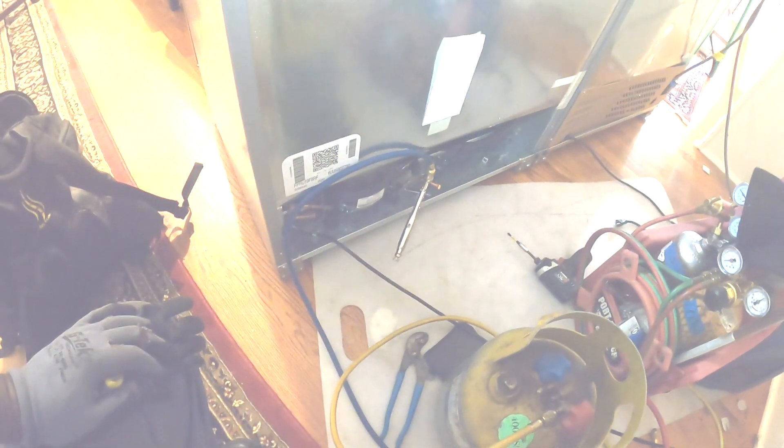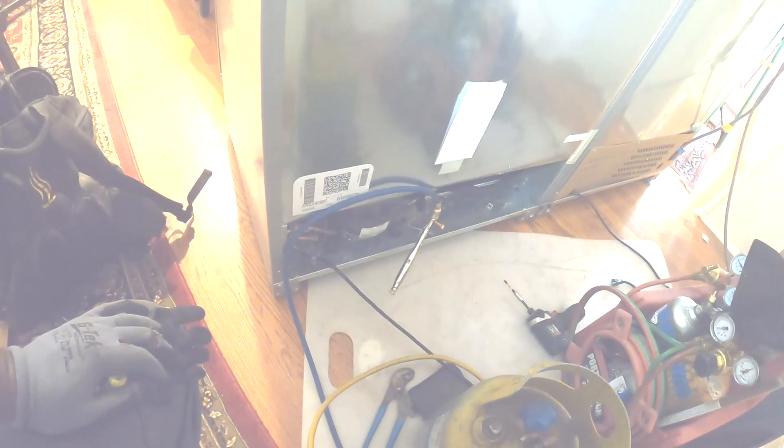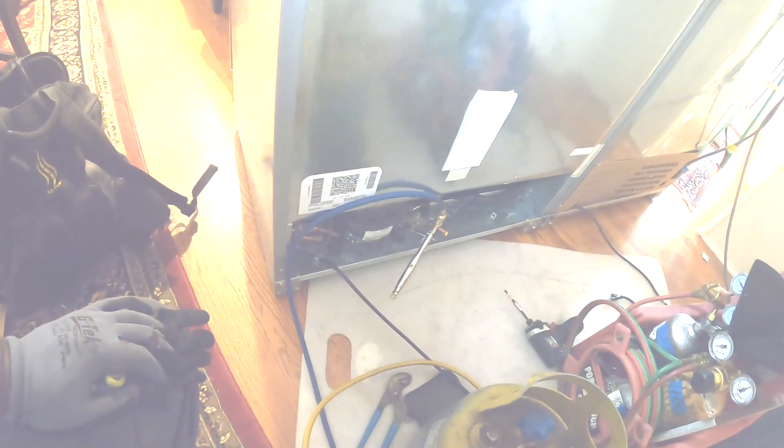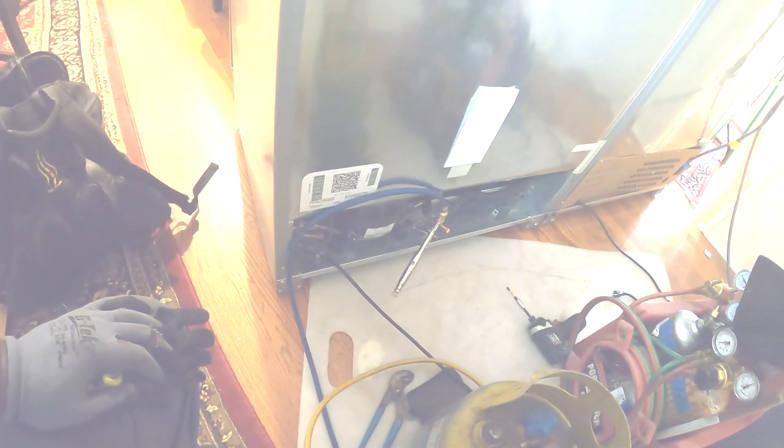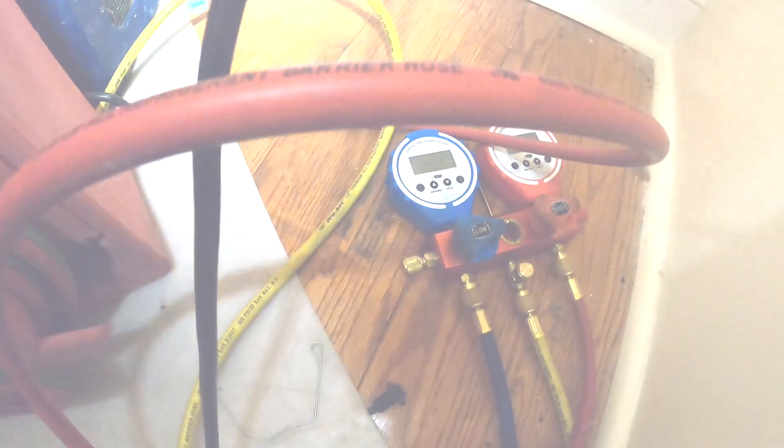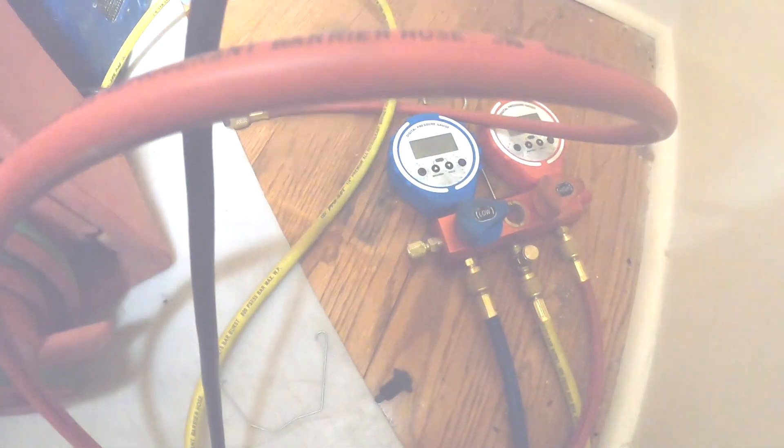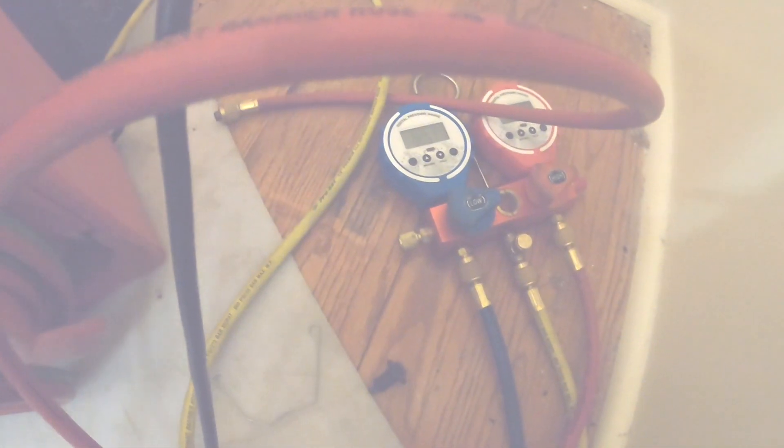I'm getting a slight frost on the evaporator coil, so I know the compressor is pushing and there's a little bit of refrigerant in it. But the frost is right there at the top, and I'm running a negative, so that's more than likely a blockage someplace.